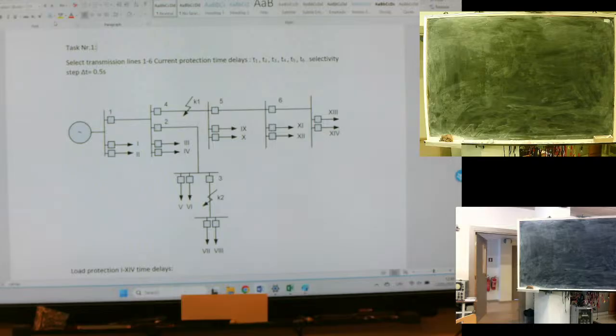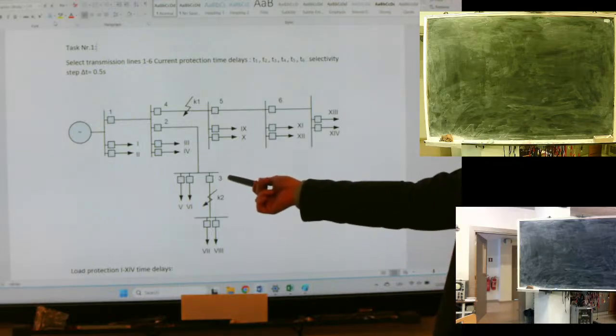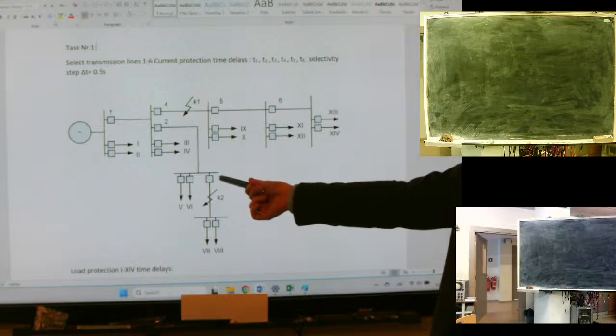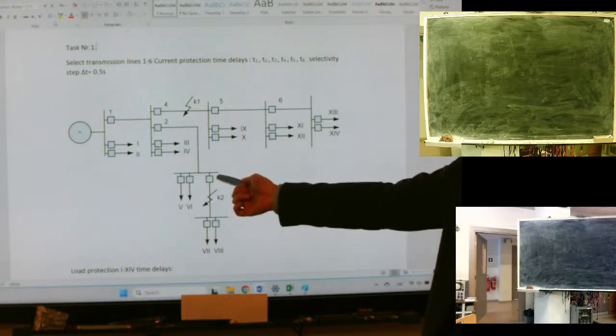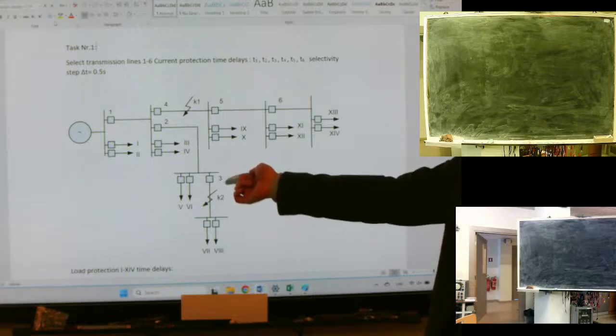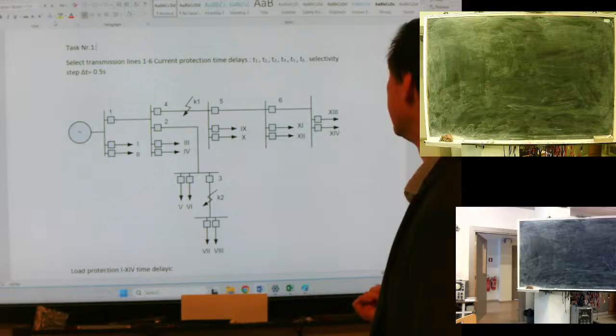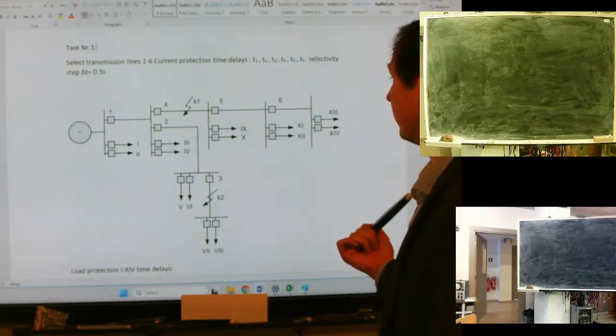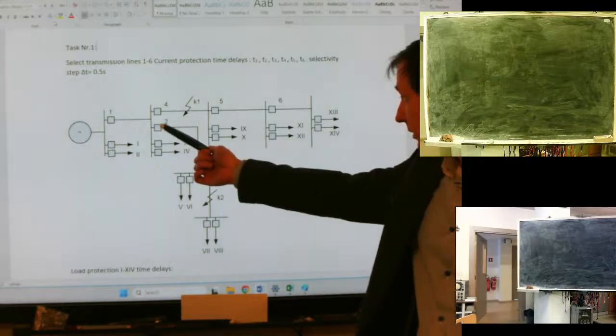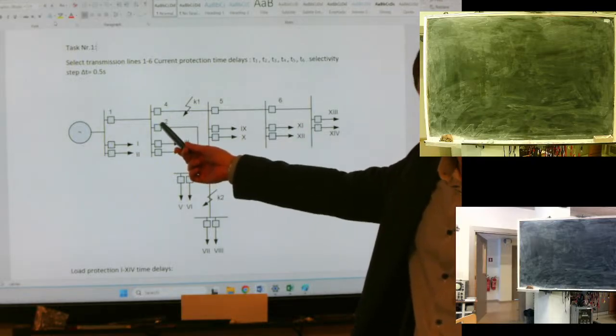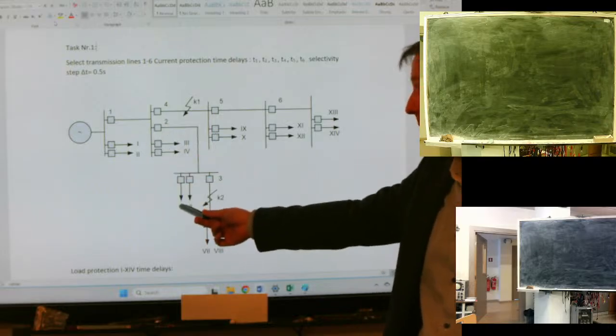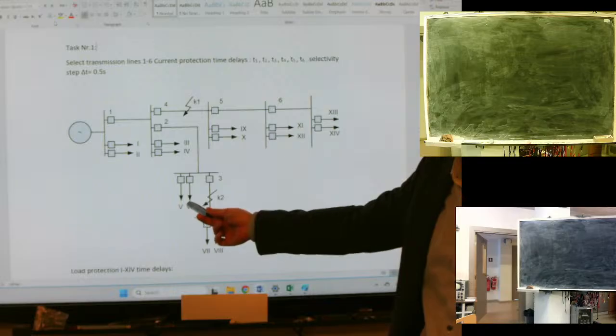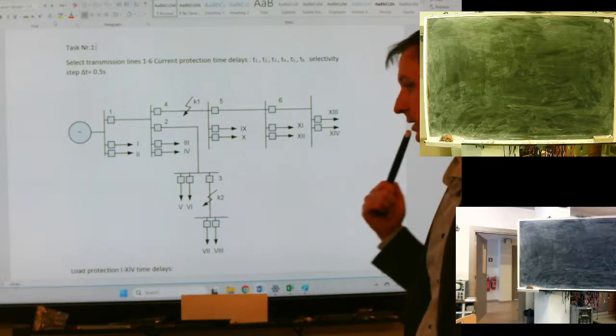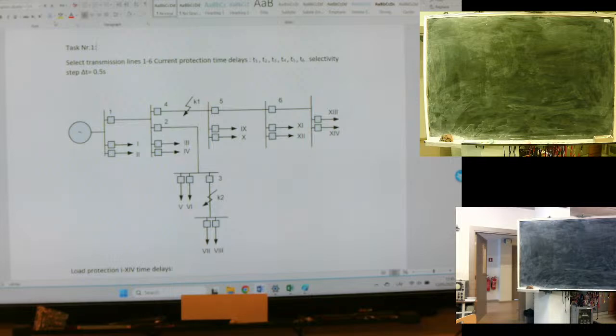Okay, we understand this issue, but how could we switch off our power breaker number 3? Or circuit breaker, yes, circuit breaker number 3. If we, for example, disconnect circuit breaker number 2, it means that we will lose the load number 5 and number 6 as well. Is it good? No, it is not good. That is the question about selectivity. Who is the first, who is the second, who is the third? So who must operate first?